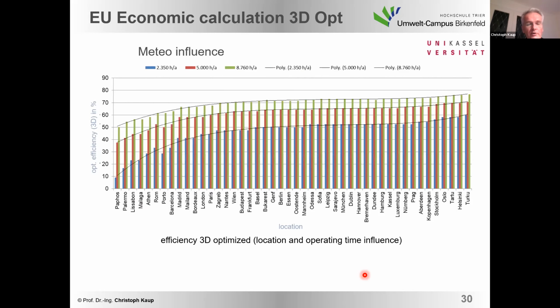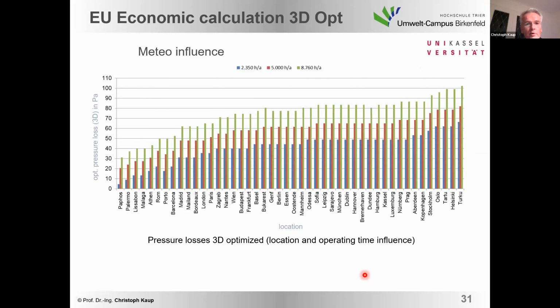So these were the efficiencies to find these optimums. You see something between 10% and 80%. Everything is represented. So we have a wide range of efficiencies which we have to use to find the optimum. And you see that the pressure losses have to be as small as possible. Even in the northern parts, it makes sense to keep the pressure loss lower than 100 pascals, for example.